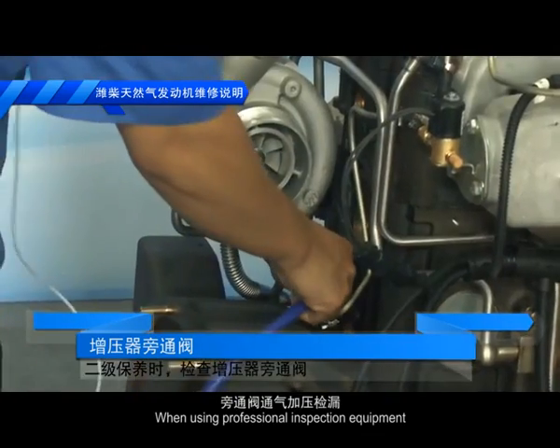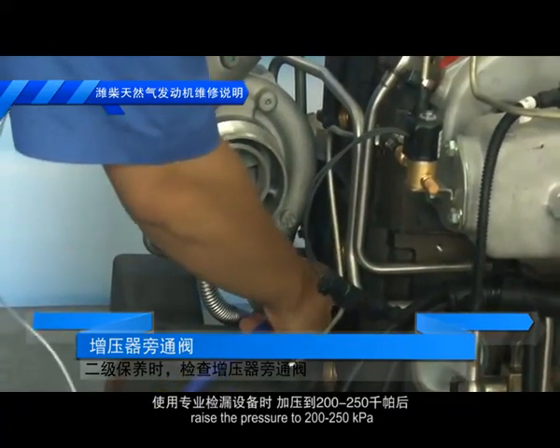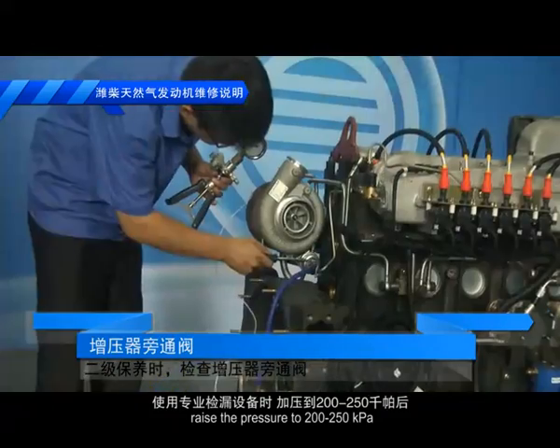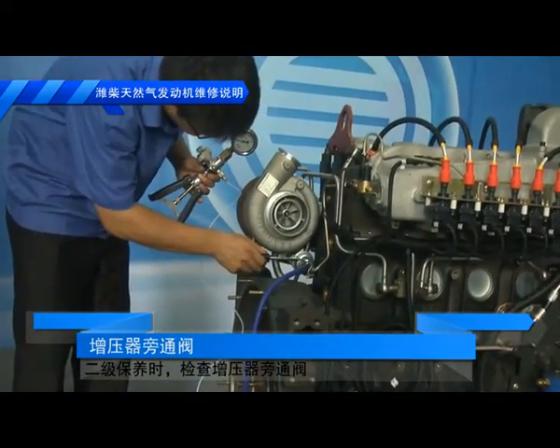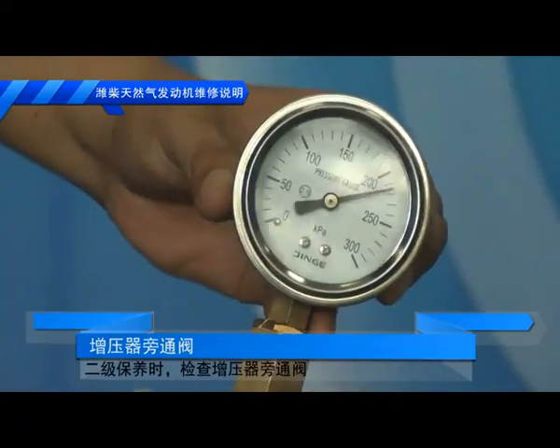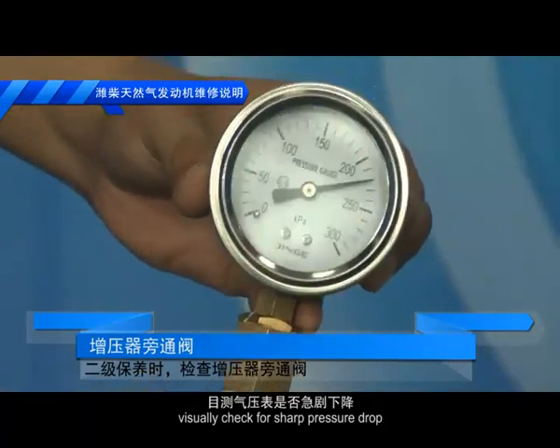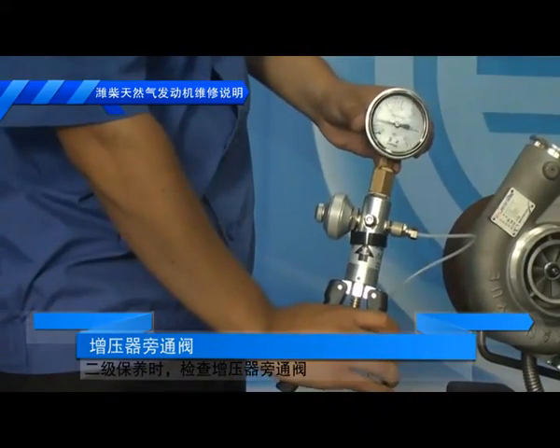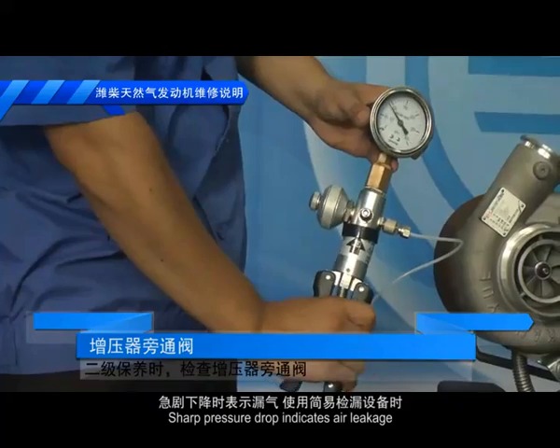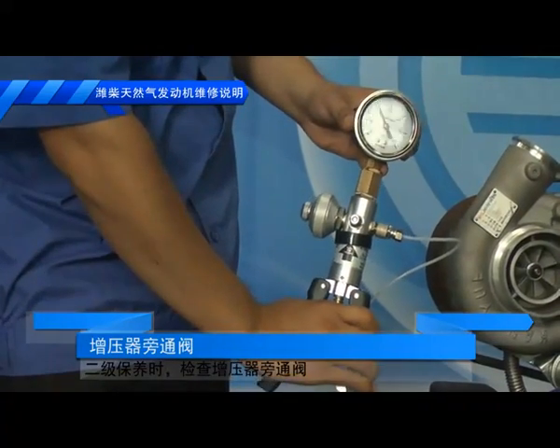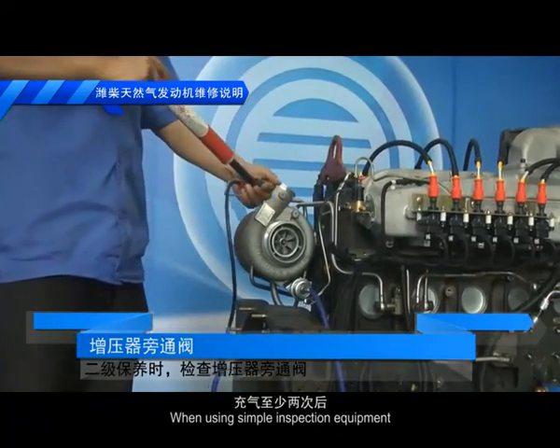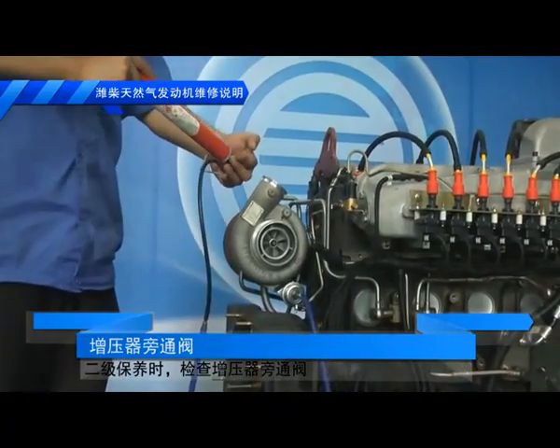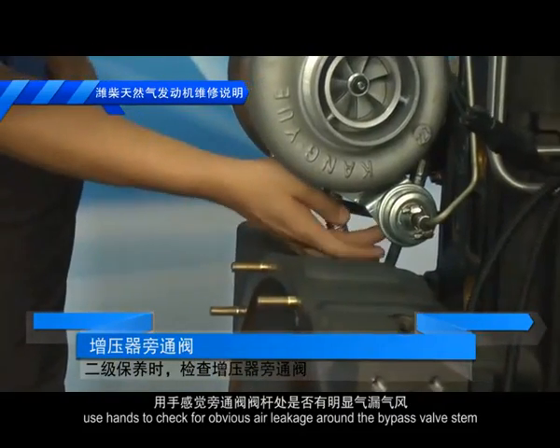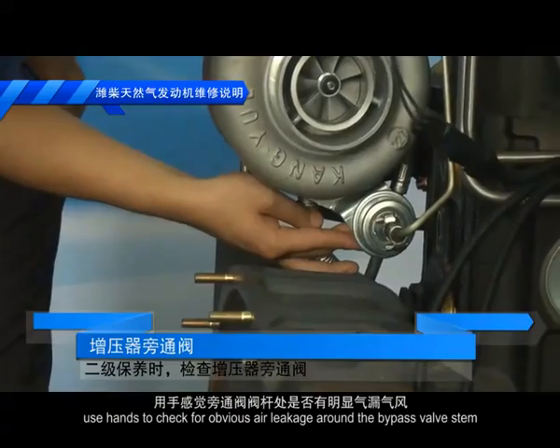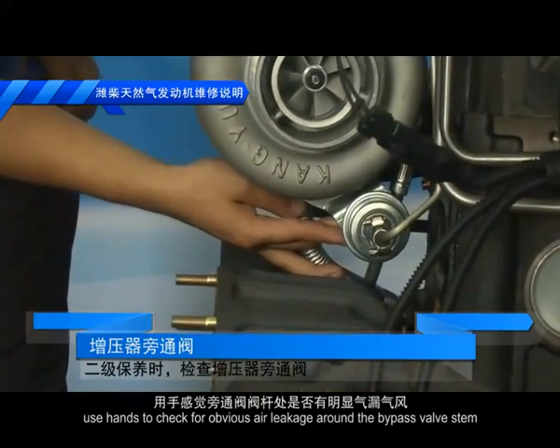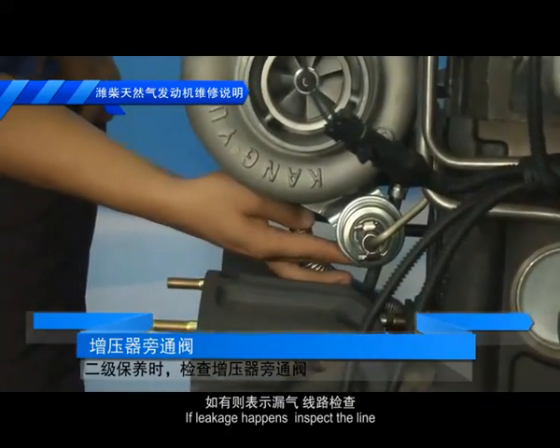When using professional inspection equipment, raise the pressure to 200 to 250 kilopascals. Visually check for sharp pressure drop. Sharp pressure drop indicates air leakage. When using simple inspection equipment, use hands to check for obvious air leakage around the bypass valve stem. If leakage happens, inspect the line.